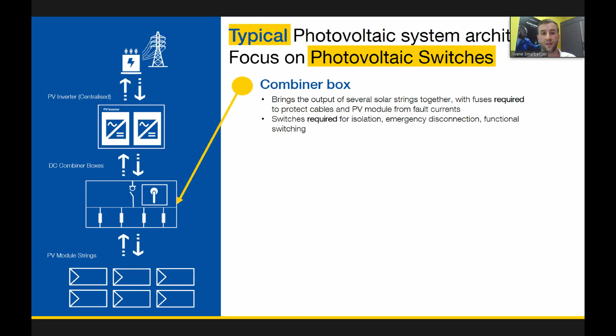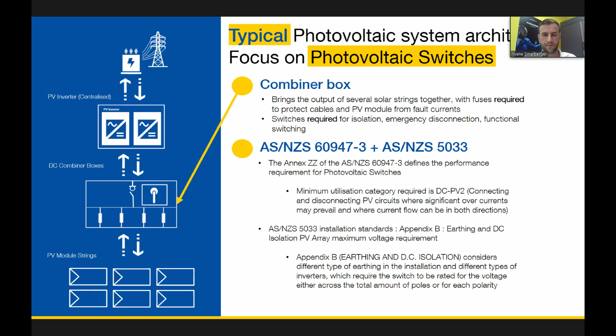When we look at the Australian standards, there are two very specific ones we should look at. So AS NZS 60947 Part 3, which defines performance required for photovoltaic switches. And then the AS NZS 5033, so the installation standards, which refer to earthing and DC isolation requirements for PV arrays. So firstly, when we look at Annex ZZ, which is AS NZS 60947 Part 3, this calls for photovoltaic switching. That if we look in the IEC world, you can have a photovoltaic switch which has a utilization category of DC 21B. It needs to switch 1.5 times its nominal current, which means that if I have a 400 amp switch, I need to be able to prove the product can work at 600 amp.